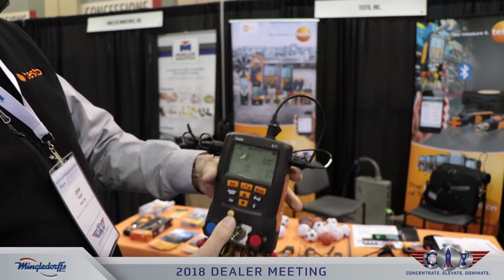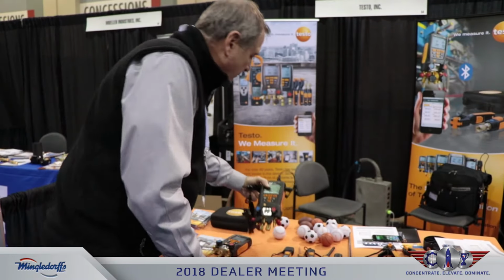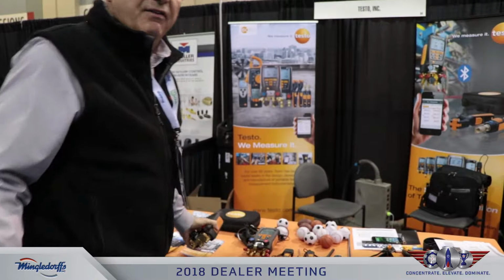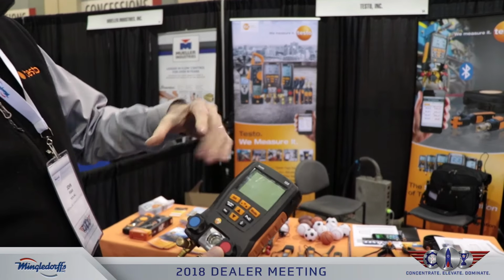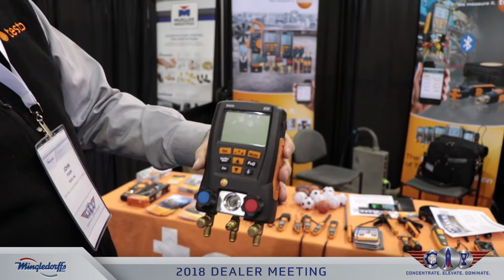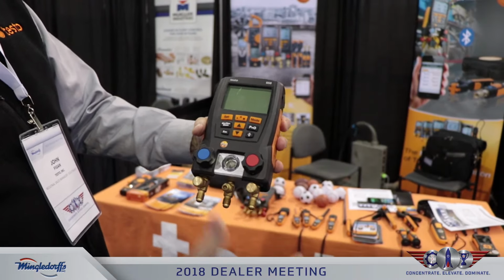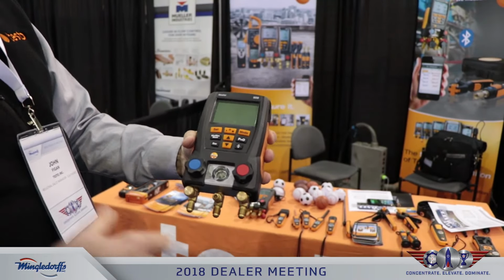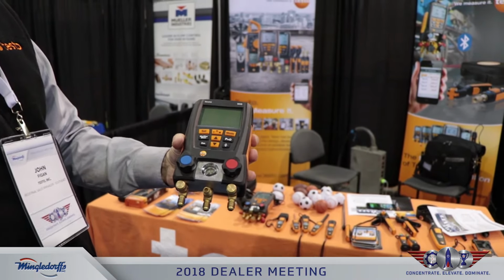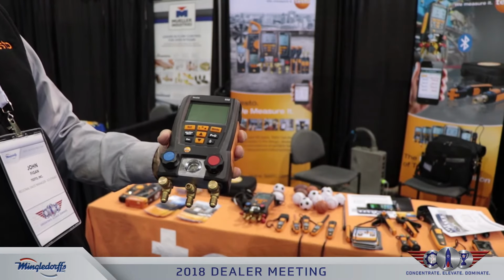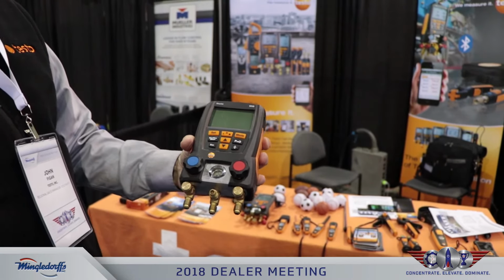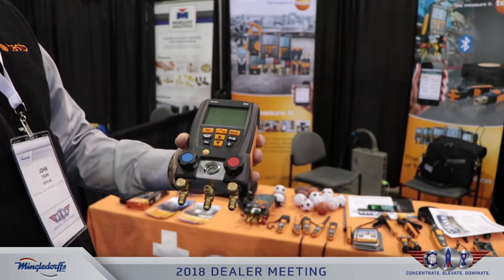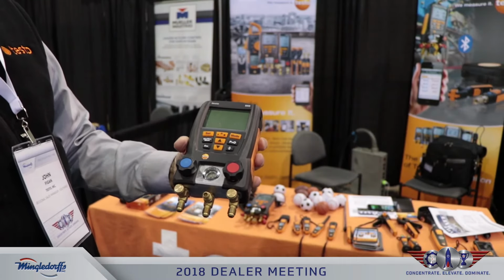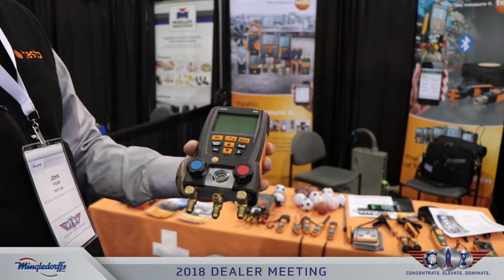They come in different models. This happens to be a 4-valve with a micron sensor. That ranges around $500. This one here has the same type of probes, without the micron sensor, this is around $300. But again, these are digital gauges, very accurate, very quick in response to calculate the correct superheat and the subcooling, so you properly charge the system.